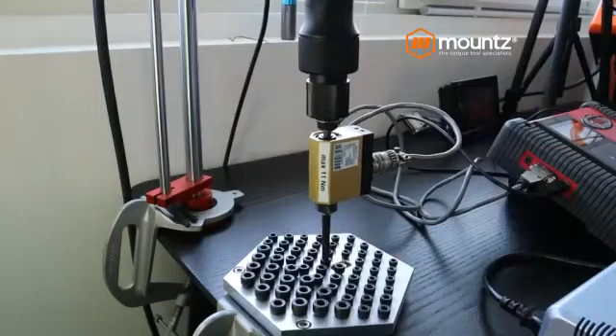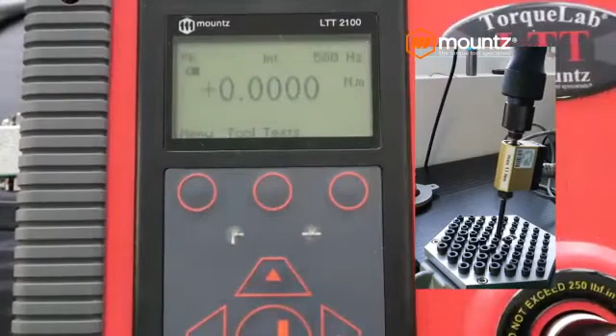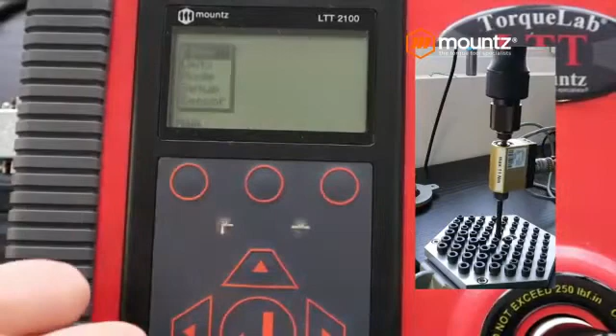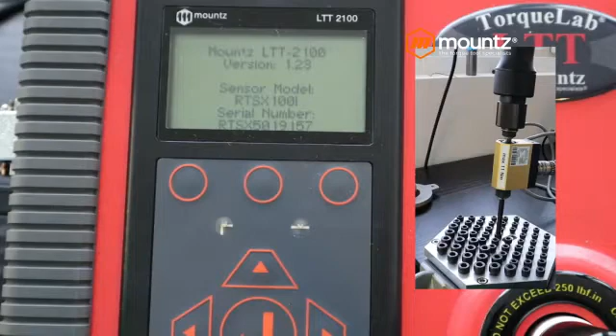Now let's move to the dynamic sensor. I'm going to mount it into the bit holder and use the screw plate to make the readings. Here on the LTT screen with the dynamic sensor, I need to indicate which sensor to consider. It recognizes the rotary sensor, RTSX 100i, and I'm ready to make some measurements.